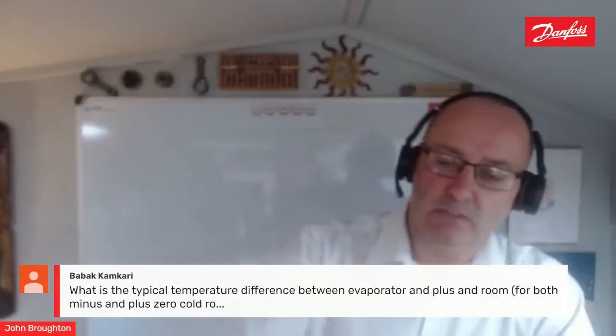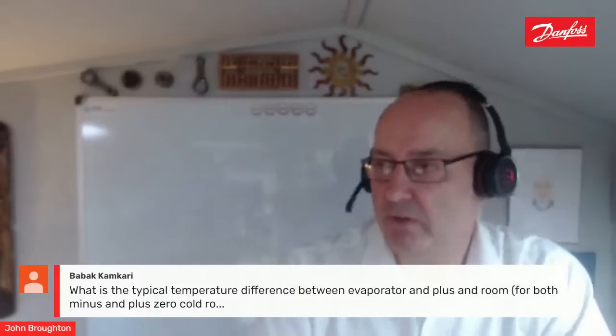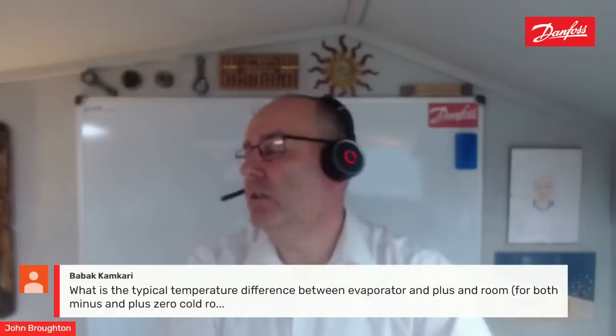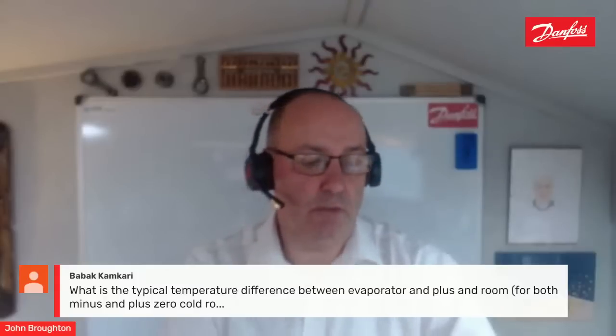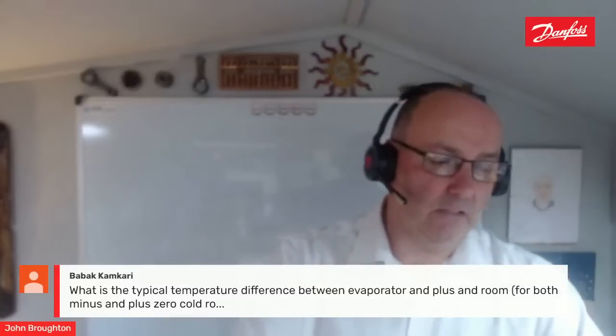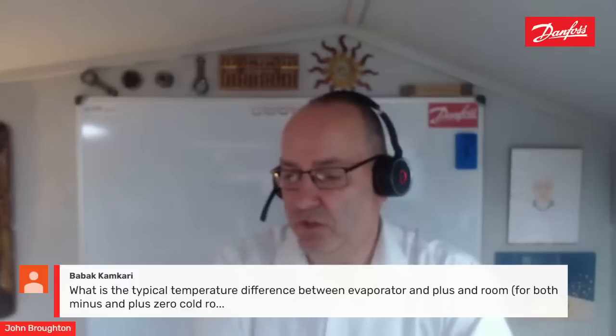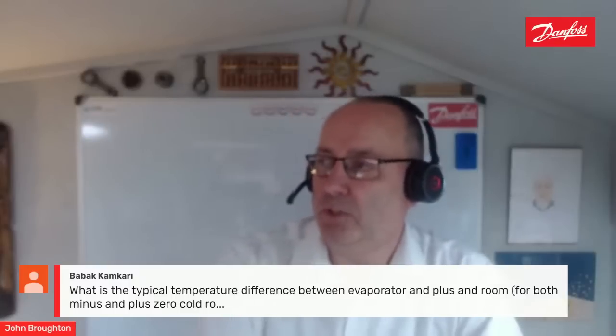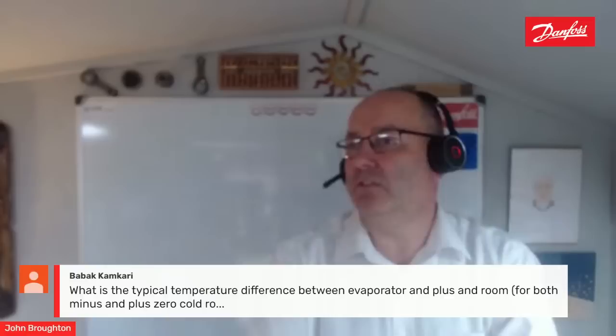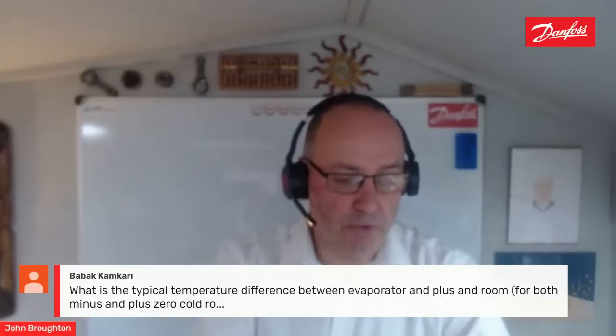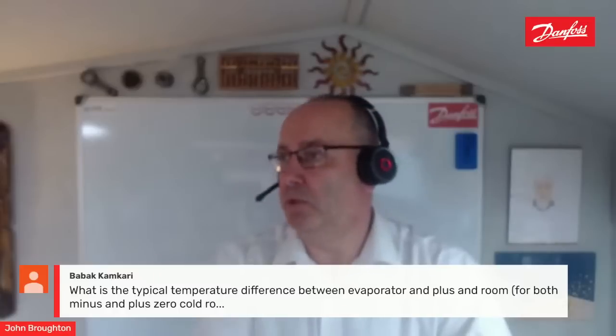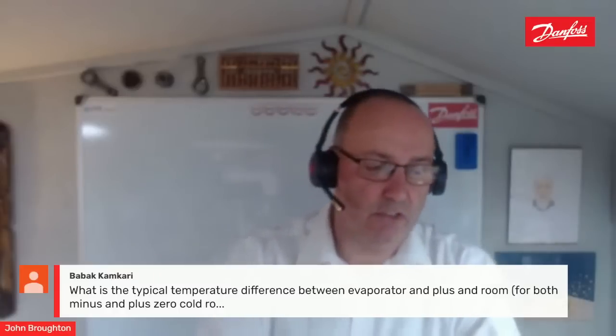There's no point dragging too much moisture out of the air, because then you're just going to put that on your evaporators, and that's going to cost more money to defrost and block up your evaporators quicker. So in a negative temperature room, humidity doesn't really count because the product's frozen already, and humidity is not going to have a huge effect on the product, but it's going to have an effect on your evaporators.